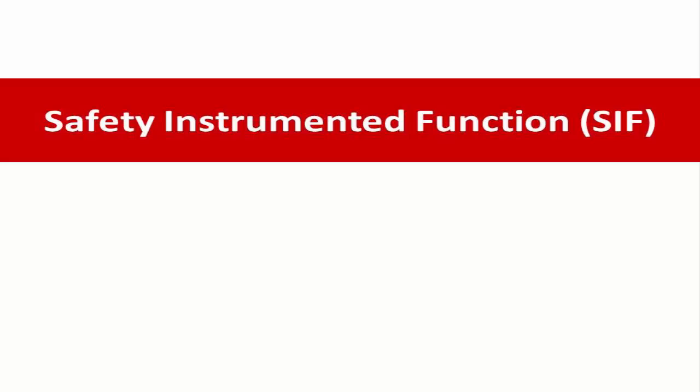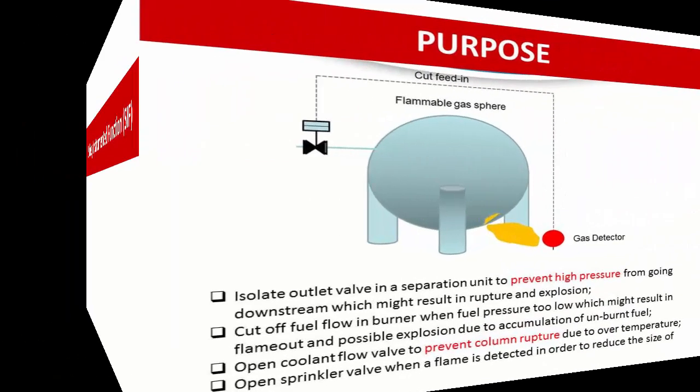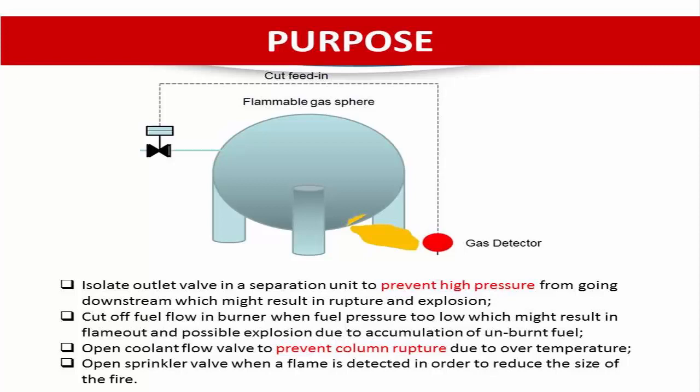A Safety Instrumented Function, or SIF, is defined based on ISA 84.00.01 or IEC 61511. It is a safety function with a specific Safety Integrity Level which is necessary to achieve functional safety — a function to be implemented in a Safety Instrumented System, or SIS, intended to achieve or maintain a safe state for the process with respect to specific hazards.